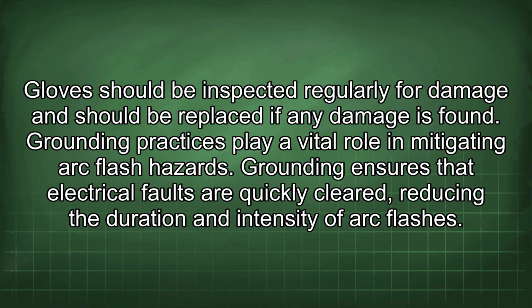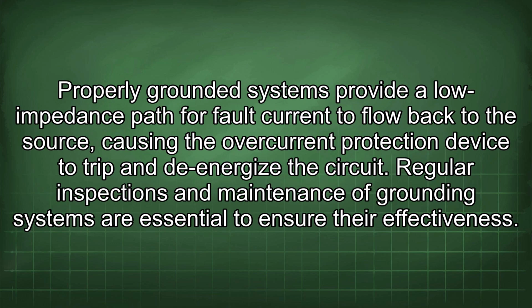Grounding practices play a vital role in mitigating arc flash hazards. Grounding ensures that electrical faults are quickly cleared, reducing the duration and intensity of arc flashes. Properly grounded systems provide a low impedance path for fault current to flow back to the source, causing the overcurrent protection device to trip and de-energize the circuit. Regular inspections and maintenance of grounding systems are essential to ensure their effectiveness.